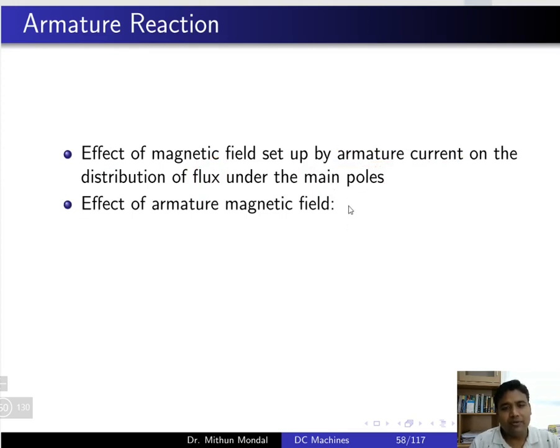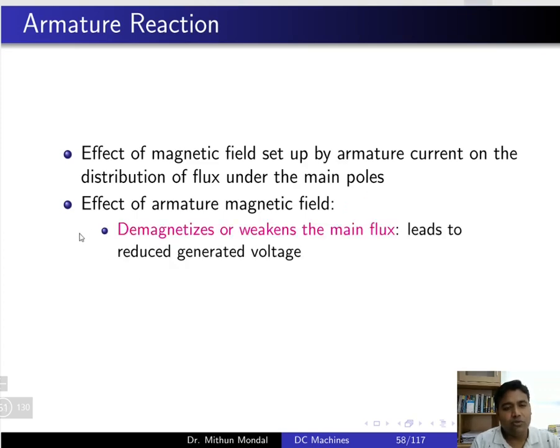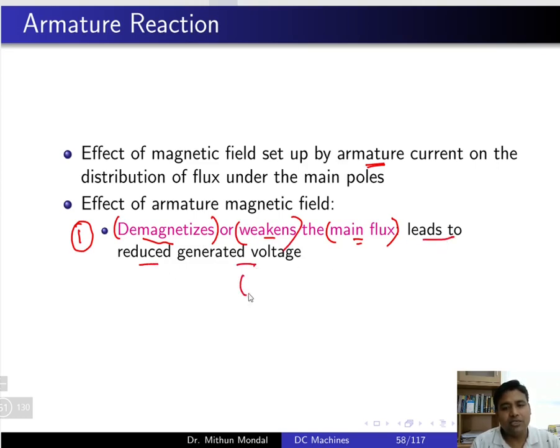What are the effects of armature reaction? There are two effects. The first effect is it will demagnetize or weaken the main flux. Since the main flux is produced by the main poles, the flux produced due to armature current will demagnetize or weaken the main flux. This will lead to reduced generated voltage — EG, whatever should be generated, will be less due to this demagnetizing property.